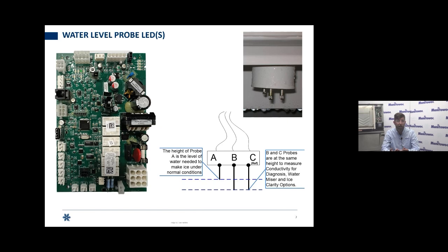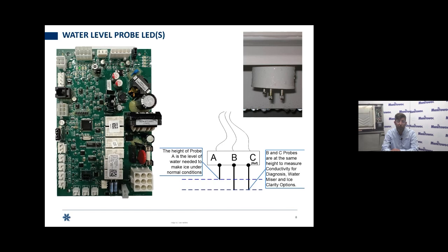But should you not have functionality on the display, you could troubleshoot the water probe utilizing these lights on the board. As you continue to fill up, then that short stick is going to end up touching that short probe. At that point, I would expect the light to the left of the low probe light to light up, letting you know that the high probe is now satisfied. Now, ideally, as you're filling, I would expect, everyone in tech support would expect, that both lights would be lit. First the low probe light, then the high probe light would light up next.